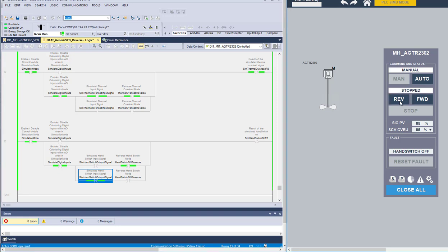The same if I try to manipulate manually the actuators, then I will get a fault. So the operator will have to reset the fault. The technician will have to have a look at the hand switch or to have it at the right position in case it was really not set correctly for the production, and then you can restart your motor.